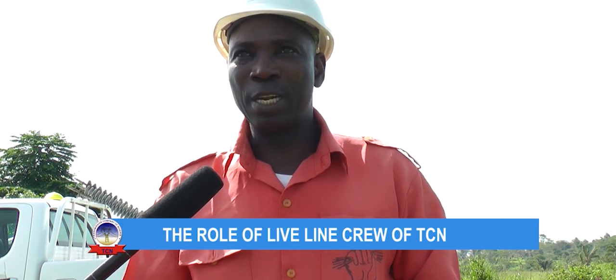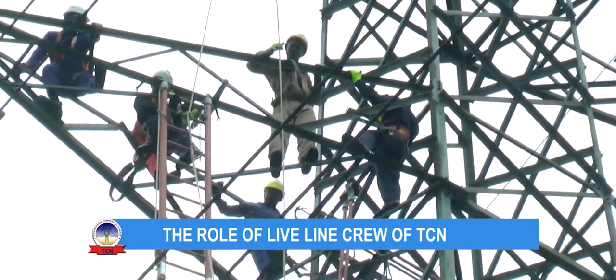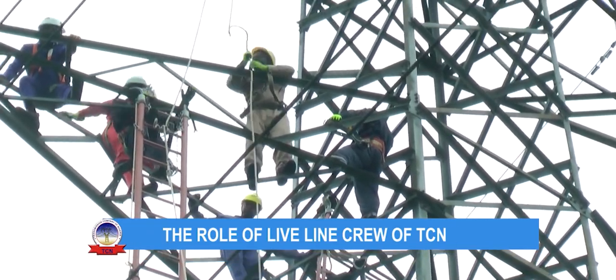The TCN official also said the crew was able to fix a power transmission line from Egbin 330kV transmission substation to Ikeja substation recently. In addition, part of our achievements recently was addressing tripping in Egbin Ikeja West, where the line passes through a cement factory and a steel company. Carbon from those companies accumulated on the line and on the insulators as particles of debris, which causes tripping.